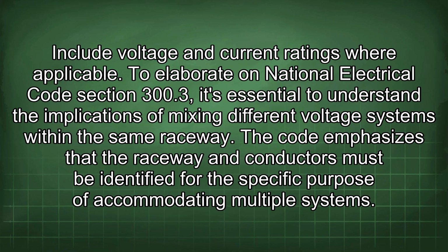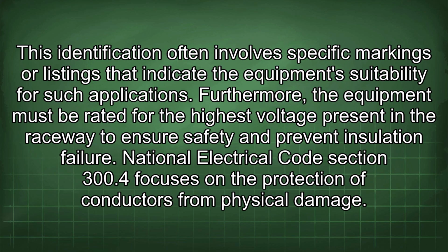To elaborate on National Electrical Code Section 300.3, it's essential to understand the implications of mixing different voltage systems within the same raceway. The code emphasizes that the raceway and conductors must be identified for the specific purpose of accommodating multiple systems. This identification often involves specific markings or listings that indicate the equipment's suitability for such applications. Furthermore, the equipment must be rated for the highest voltage present in the raceway to ensure safety and prevent insulation failure. National Electrical Code Section 300.4 focuses on the protection of conductors from physical damage.